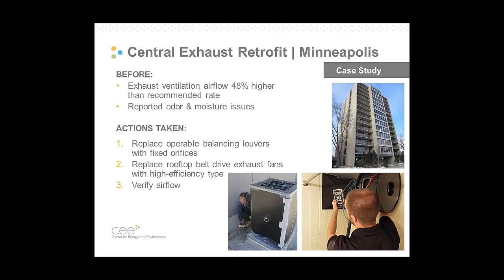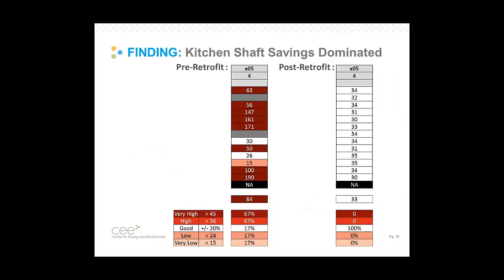So here's a retrofit that we did in Minneapolis again. We measured their exhaust ventilation flows at 48% higher than the recommended rate for the building, and they were having odor and moisture issues, particularly in their bathrooms. The retrofit entailed replacing the operable balancing louvers, like we saw in the picture before, with fixed orifices, the sheet metal with the hole in it, and replacing the rooftop belt drive exhaust fans with high efficiency types with speed controls. Then we did a pre and post airflow measurement.